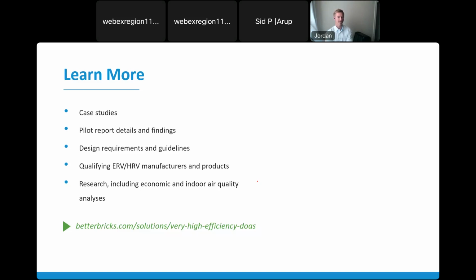There are also a few other aspects of those requirements that I didn't touch on today. We like to see ultra low cross-flow leakage. We also like to see efficient defrost control, which can pop up when you're recovering in very cold conditions at a very high recovery rate. And then we also have a few other requirements just on insulation and control strategies, some best practices. And so we maintain a list of compliant products. When we first started these demonstration projects, there were very few ERVs and HRVs that met these requirements, but that list has expanded, and there are currently over 6 manufacturers and over 100 different products that can meet these requirements. So they're out there. There are some very good products.